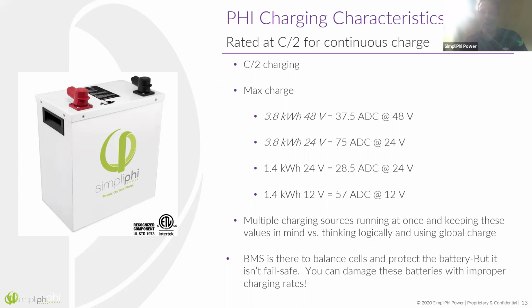All of our batteries are rated at a C/2 continuous charge rating. What that means is that the battery's capacity is delivered in 2 hours. That's how quickly we can deliver current to this battery. So if we have a 75 amp hour battery and we want to charge it in 2 hours, we would be limited to 37.5 continuous amps at 48 volts. Another way to think of this is if we're charging the full capacity of a 3.8 kilowatt hour battery in 2 hours, we're delivering half that capacity per hour. So this battery will charge at 1.9 kilowatts continuous. There is no surge for the charging cycle either.